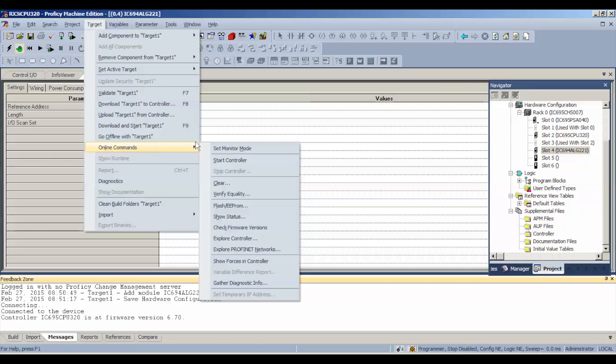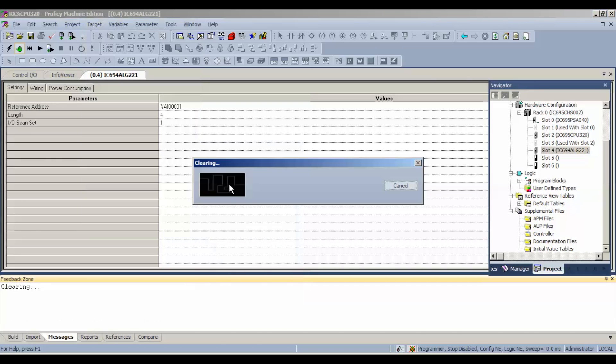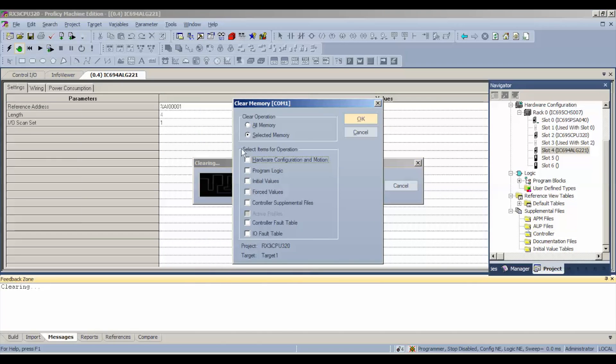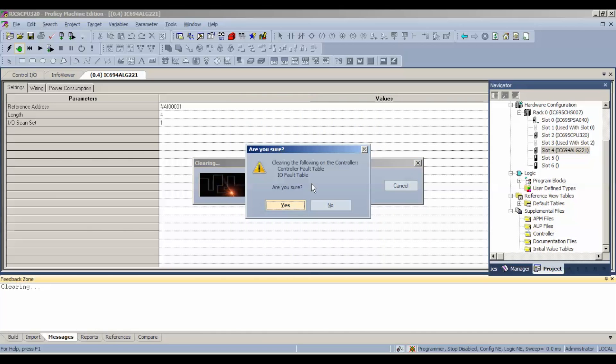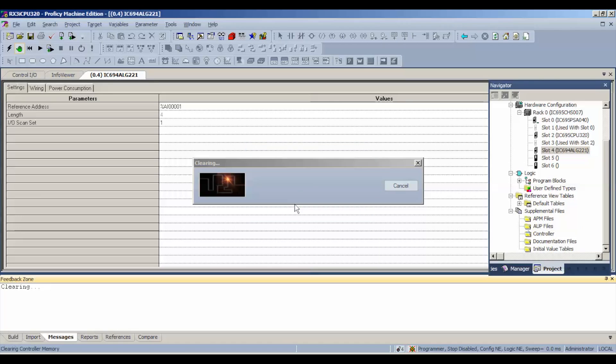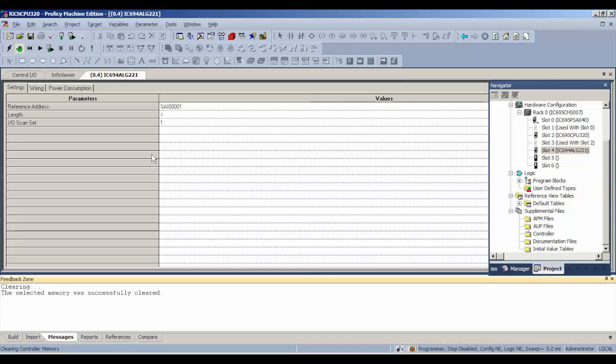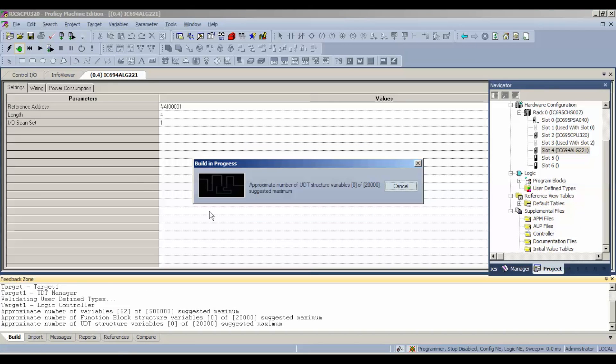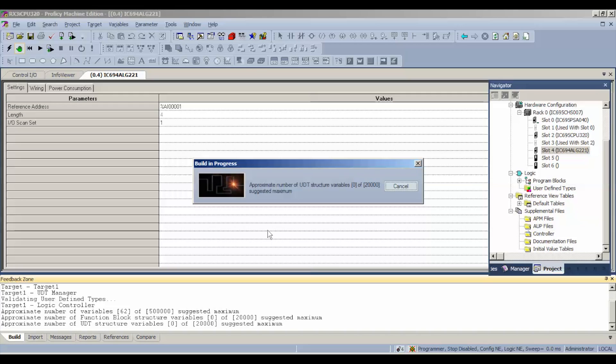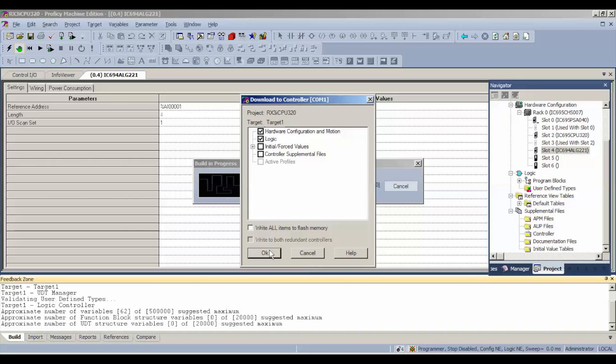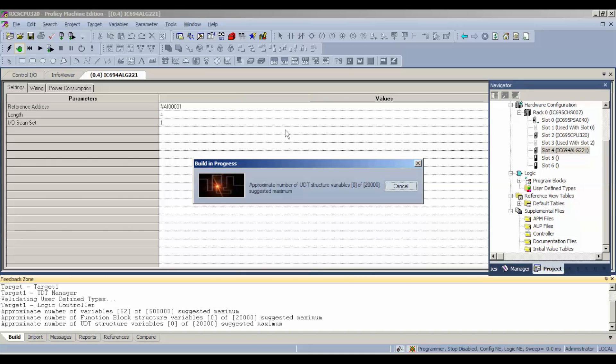For that reason, I'm going to go to online commands, go to clear. We want to clear controller fault and IO fault tables. The reason we're doing this is, as I said before, when we go to download and run, which we're going to do right now, if those aren't cleared and the processor was doing a different function before, it's going to fault because it hasn't been downloaded yet and it doesn't know this ALG221 we want to test. Make sure you clear those.